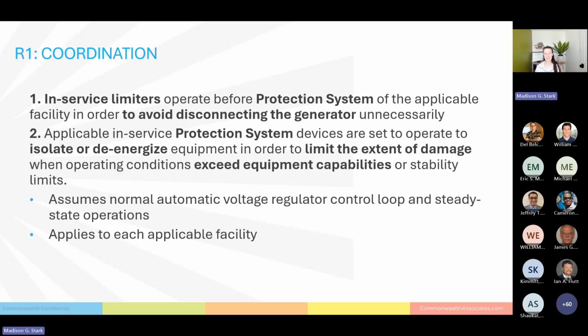The second requirement is that the protection systems are set to isolate or de-energize equipment if operating conditions exceed equipment capabilities. So we have a 2-step approach here under PRC 19. The first is that we want to curtail generation if possible to keep the generator up and running safely. The second is that in the event that we can't keep the generator running safely and we're risking equipment damage, then we need to disconnect the generator under the protection system. This regulation does assume steady state operations with an automatic voltage regulator control loop. That's important because it differentiates it from some of the other regulations, where we're really focusing on steady state operations for the generator.